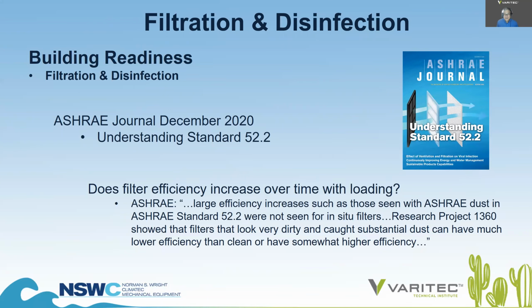Research project 1360 showed that filters that look very dirty and caught substantial dust can have much lower efficiency than clean, or, you're gonna love this, have somewhat higher efficiency. So just be aware there's no catch-all absolute application that is going to result in some absolute catch-all result. It varies building per building. And if you want to study that article in greater detail, I recommend you go to the December 2020 ASHRAE Journal for that article.